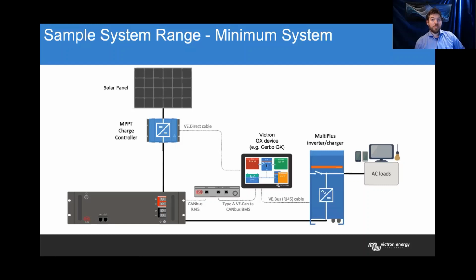These control cables are important when connecting to a battery like the BYD Flex, because the BYD Flex and the BMU will send charge parameters to the rest of the system, and the rest of the system will adapt its behavior accordingly. So if the battery is full, it'll stop charging and send that signal to stop charging. If the battery is empty, it'll send the signal to the inverter charger to stop discharging and protect the battery.